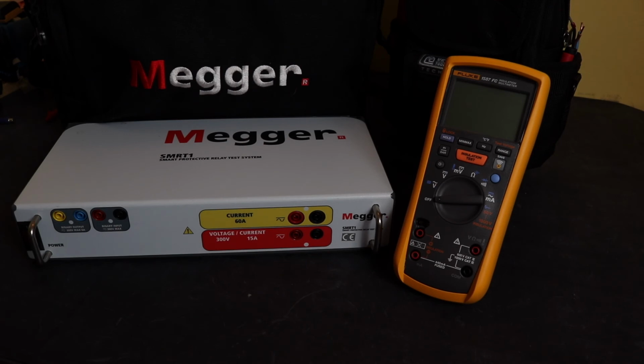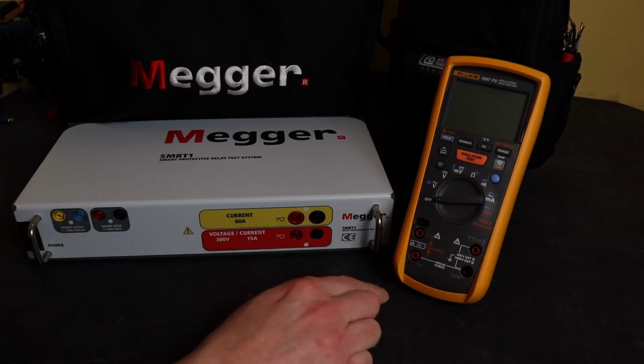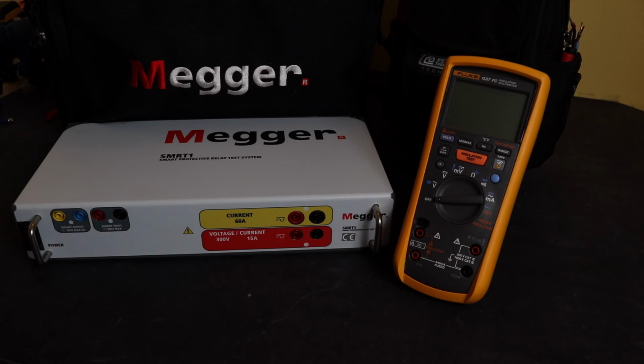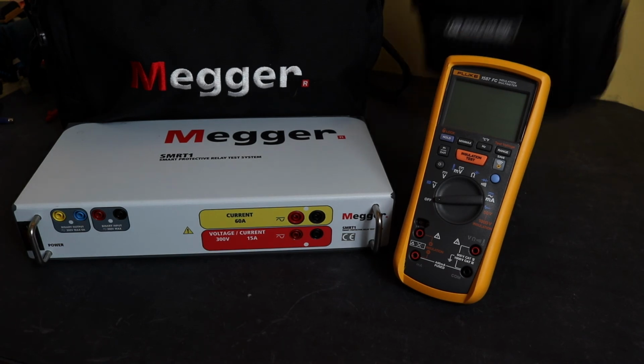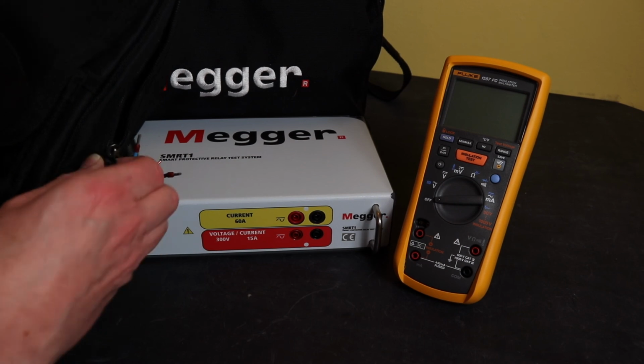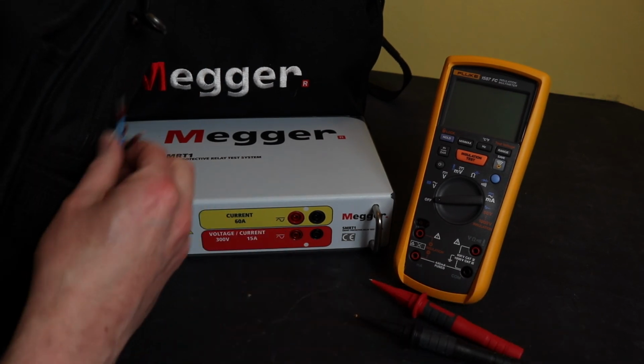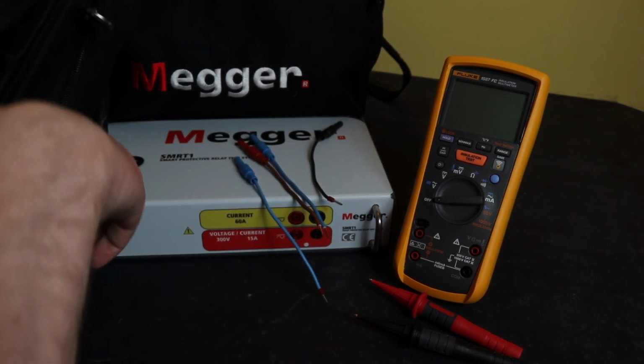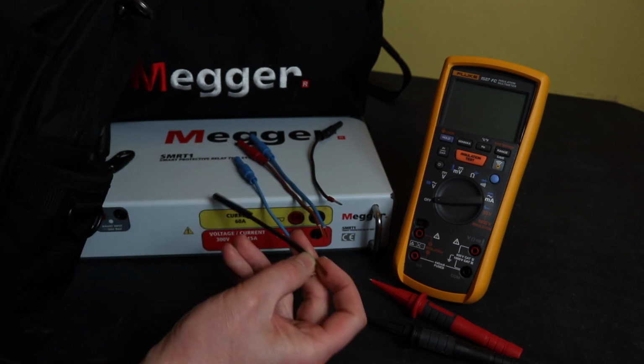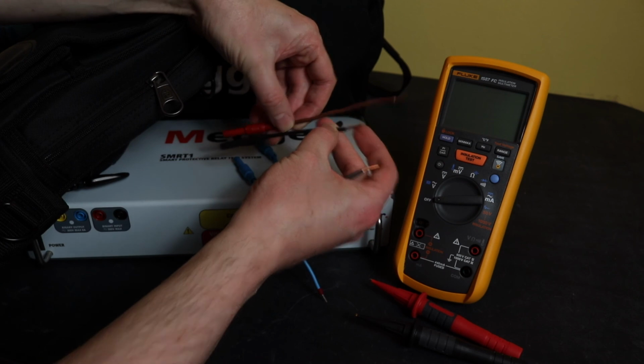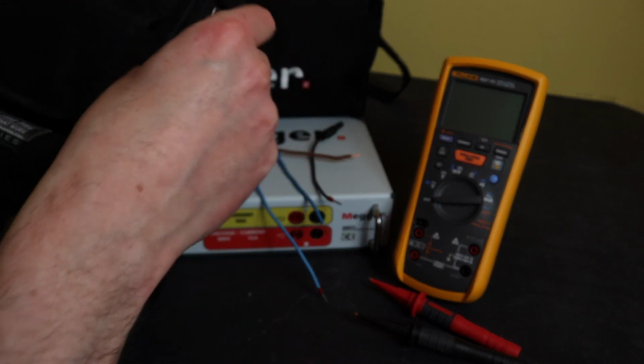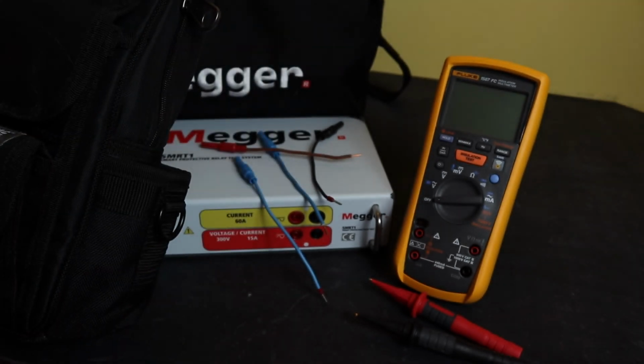Okay, so that's my test setup there for field testing transducers. I'm using the Megger SMRT1 and Fluke 1587 FC there that I keep housed within the Veto MB2 meter bag. There is only one element that I would probably change with the physical setup that I have here. These adapters that I put in the side pocket here, out of the way. The four here that I've made up myself, they're all okay. It's actually the purchased ones that I got from, I think it's a Staubli, I got them from. They're quite a bit shorter. And then the other ones, as a consequence, disappear right inside the side pocket there, and I lose them a little bit.